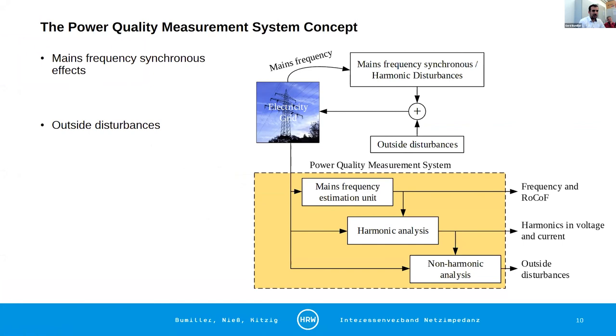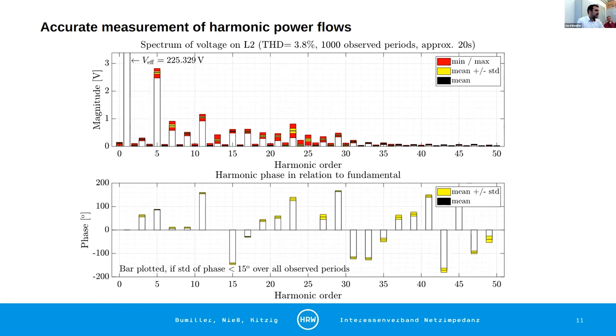We have these mains frequency synchronous effects and we have these outside disturbances, and we want to perform at first a harmonic analysis and then a non-harmonic analysis. So we want to be able to separate those two effects again that are taken into account in our model. We want to orthogonalize at first the frequency. We have a mains frequency measurement, and with this mains frequency measurement we can perform a harmonic analysis. We can extract everything that is harmonic, so synchronous with the mains frequency. Then we can take this information to subtract all the non-harmonic information that is in our grid, for example in the voltage or currents that we measure.